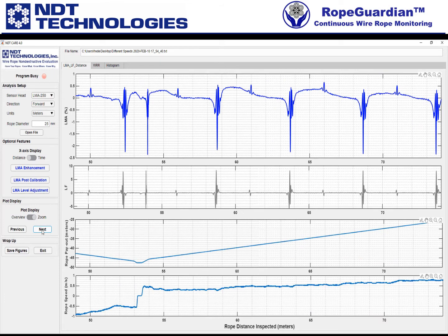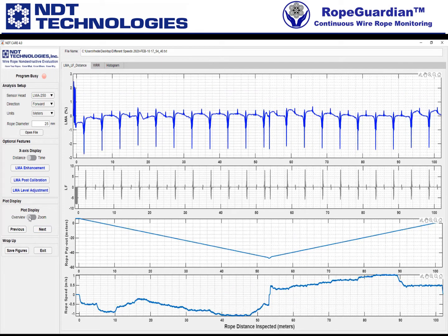So that's that. Down below we can save or exit. Let's walk through quickly the enhancement — I'll click this, and this is just based on the sensor head that we've provided. As you watch me click the button, you can see this has sharpened up — we talk about echo effects and other things, but basically it's one way to clean up the signal.